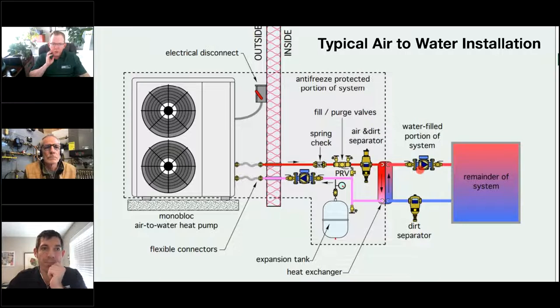Yeah, and a lot of the units where they have a packaged outdoor-indoor unit, you have to be aware that the indoor unit typically has a built-in pump. Like the one that is installed in John Siegenthaler's house that Eden Energy is distributing, it's got an integrated pump. So you have to pay attention to that. It is a good pump.